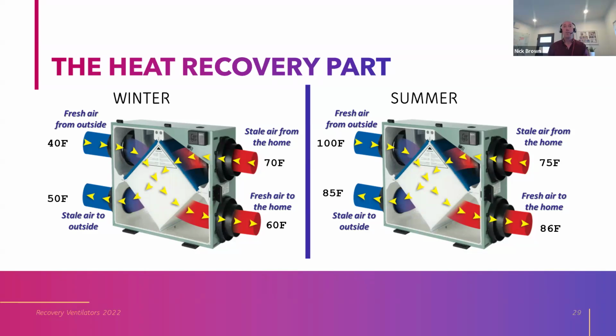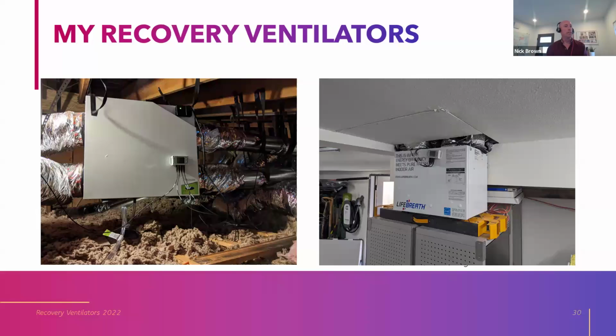Most, it's a bargain you make that you run it 24/7. Most of the time it's beneficial. Some of the time it's slightly less beneficial. But some of them have a summer cooling bypass function, for instance, that does exactly what you're talking about. When it's cooler outside, it routes the air around the heat exchanger core. So you're bringing in fresh filtered air without heating it up. Good question. We were going to talk about that, but it came up earlier.